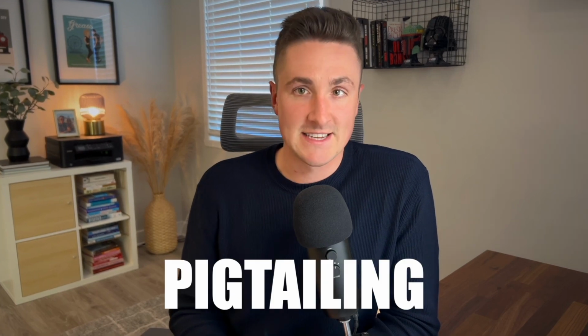Thankfully, insurance companies don't actually require you to replace all the aluminum wiring in your home because there's another option that's called pigtailing. Aluminum wiring itself is actually a perfectly capable conductor of electricity. The issue occurs when the aluminum wires are connected to connectors such as outlets, and that's where pigtailing comes in. With this method, rather than having aluminum wires make the connection, they'll actually add a short piece of copper between the outlet, for example, and the aluminum wiring, which basically eliminates the increased risk of fire hazard and satisfies the insurance company's needs.